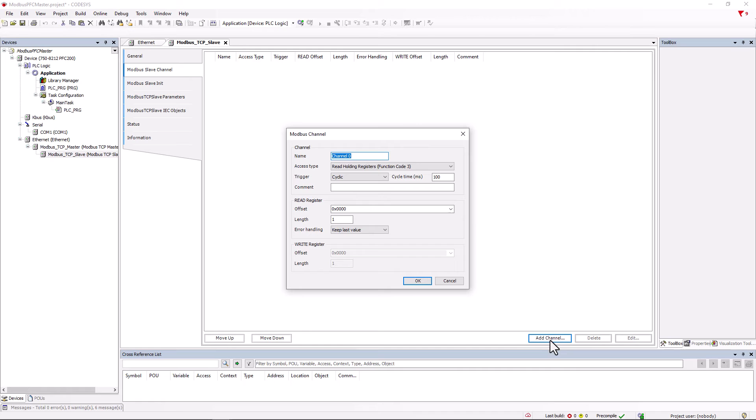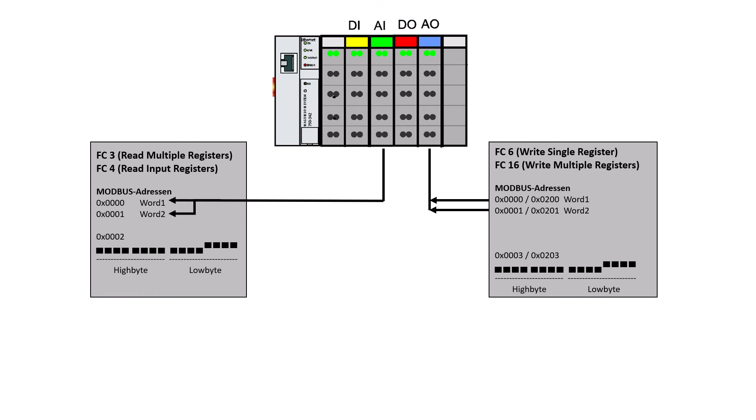One possibility of channel assignment is that each module is assigned to its own channel depending on its installation position. It is also recommended to access digital signals with coil functions and analog signals with register functions. Here is a small graphic to illustrate this.